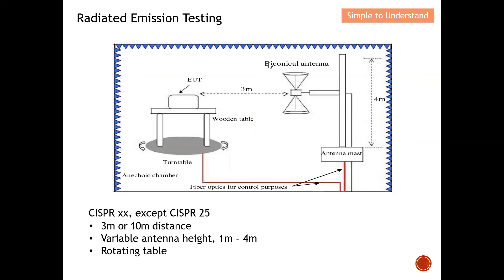This diagram shows the setup for Radiated Emission testing. This setup is valid for all CISPR standards except CISPR 25, which I'll explain on the next slide. For the remaining CISPR standards — such as CISPR 11 and CISPR 22 — this setup applies. One key point: the distance between your EUT and the antenna can be either 3 meters or 10 meters, and in some cases even 30 meters, though nowadays 3 meters and 10 meters are most common.